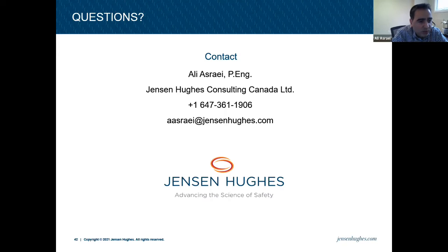It means contractor, fire department official, fire alarm technician, testing the smoke control system. I think the first step is to involve an engineer. I mean, fire department, yes, they can go ahead and test the system or ask for your records, and at that point you need an engineer to get involved to give you the test, the maintenance procedure, or the satisfactory operation.